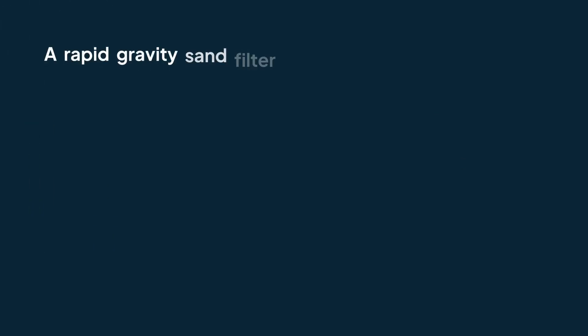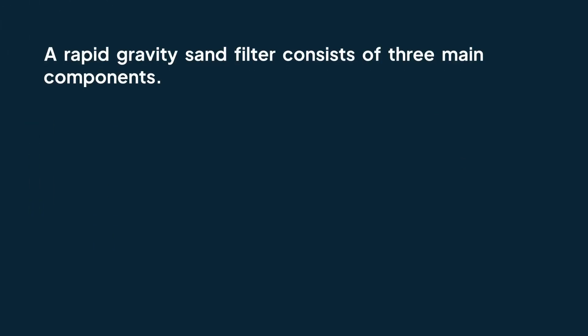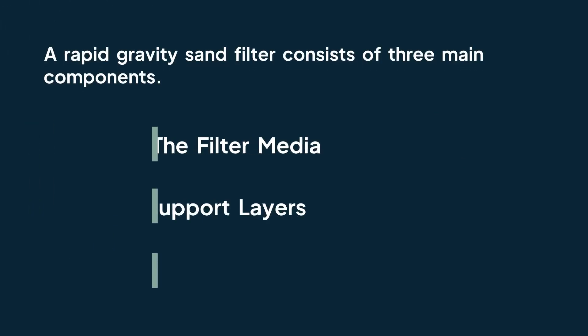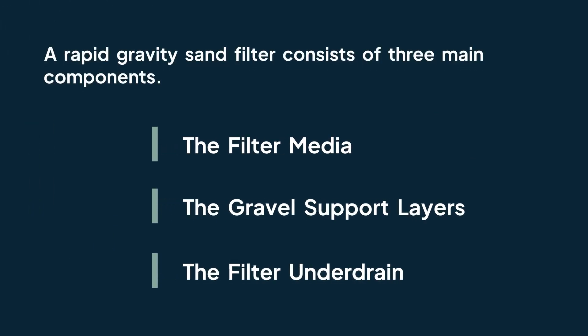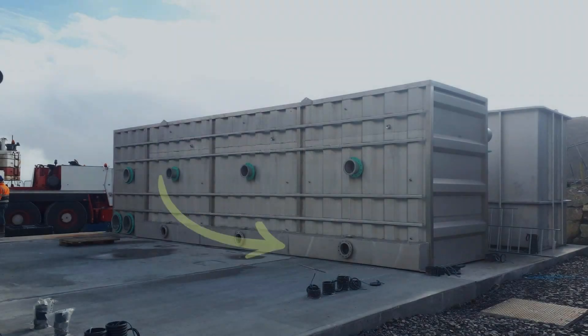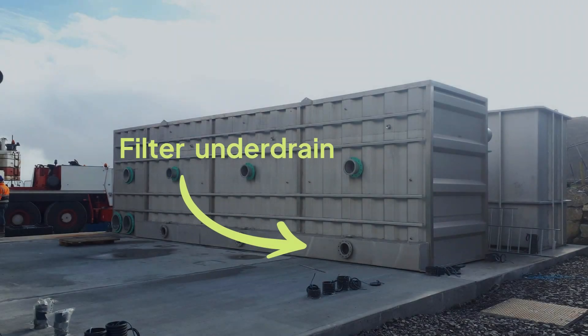What parts make a rapid gravity filter? The rapid gravity sand filter consists of three main components: the filter media, gravel support layers, and the filter under drain. The under drain plays a crucial role by supporting the filter medium and gravel evenly, and collecting the filtered water from the filter's bottom.